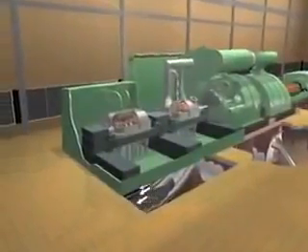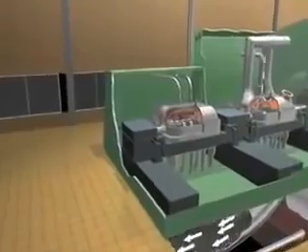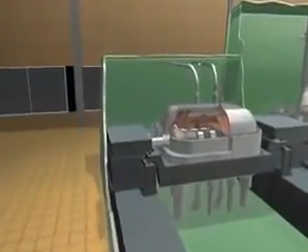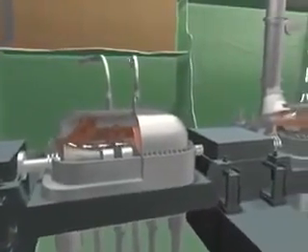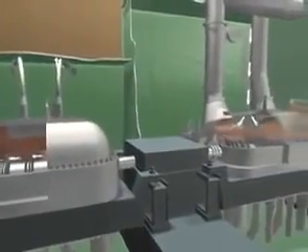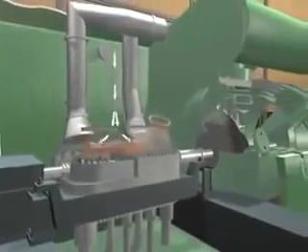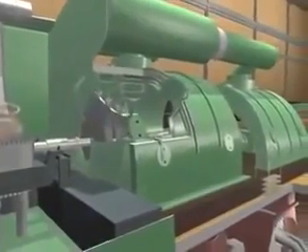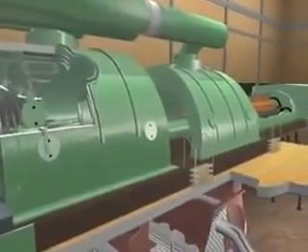High-pressure steam, now 1,000 degrees Fahrenheit at 3,500 pounds per square inch, is piped from the boiler to the first in a series of turbines. Here it expands between layers of turbine blades mounted on the turbine shaft. The steam loops back to the furnace, then on to the second turbine. In this process, the steam turns the series of turbines 3,600 revolutions per minute, providing power to the generator, the last in the series of machines.